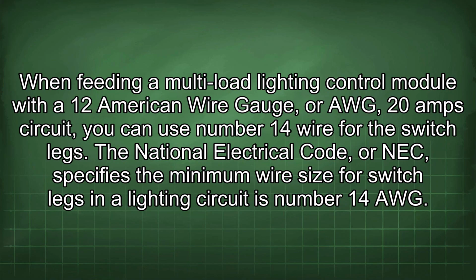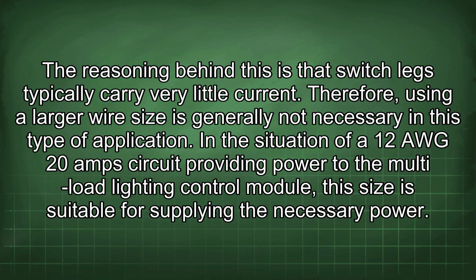When feeding a multi-load lighting control module with a 12 American wire gauge, or AWG, 20 amp circuit, you can use number 14 wire for the switch legs. The National Electrical Code, or NEC, specifies the minimum wire size for switch legs in a lighting circuit is number 14 AWG. The reasoning behind this is that switch legs typically carry very little current. Therefore, using a larger wire size is generally not necessary in this type of application.